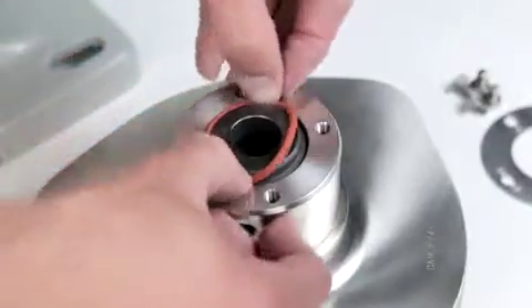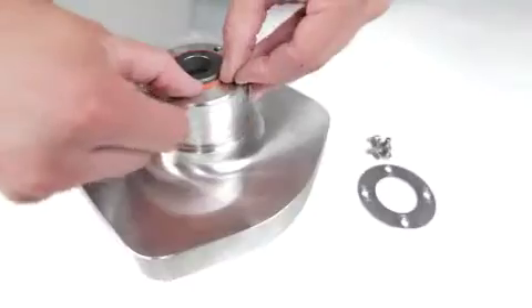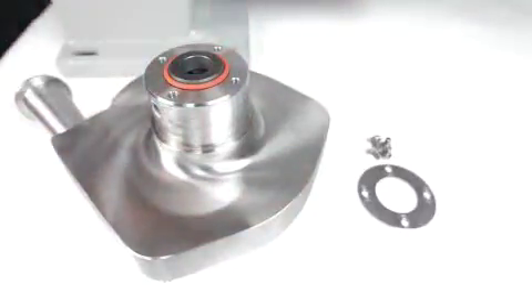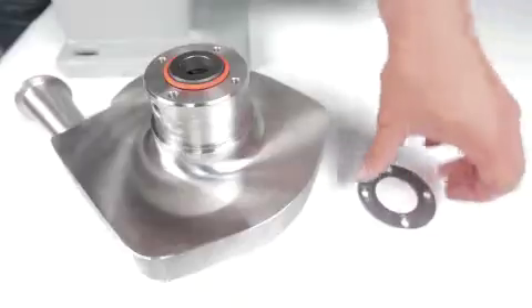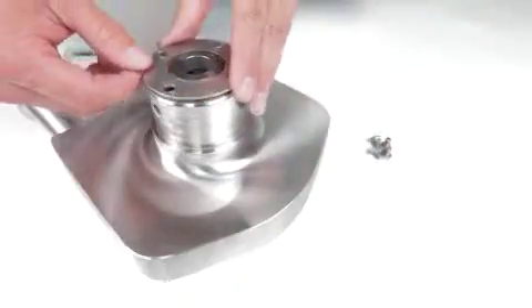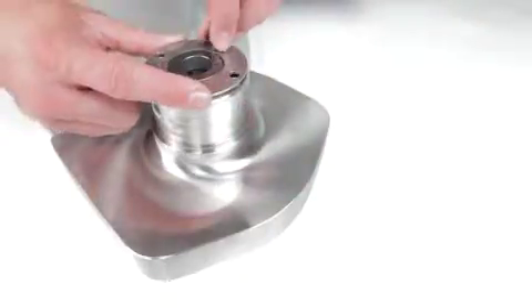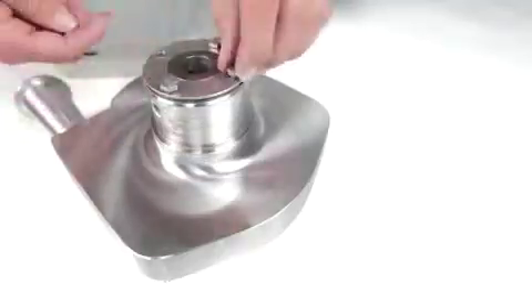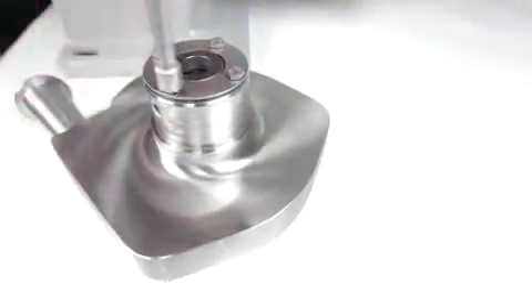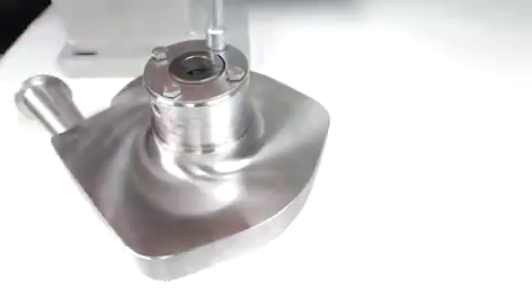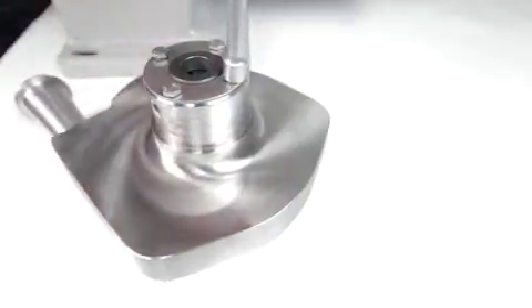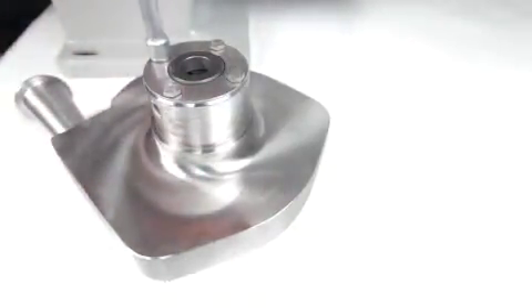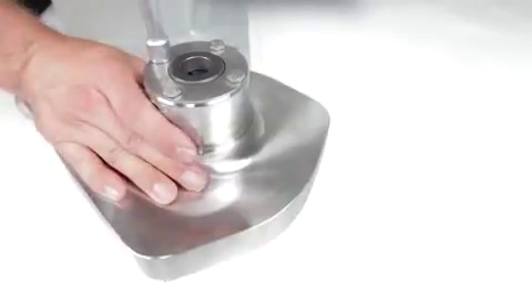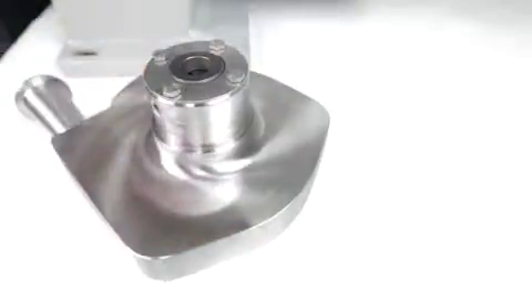Install the stationary seal O-ring onto the back of the stationary seal. Do not lubricate this O-ring. Improper fit may cause leakage or seal damage. Place the retaining ring on the housing hub, aligning the holes in the retaining ring with the holes in the hub. Thread the 4 retaining ring bolts through the holes in the stationary seal retaining ring and into the housing hub. Alternately tighten the bolts so that the retaining ring secures evenly. Uneven tightening could result in seal damage.